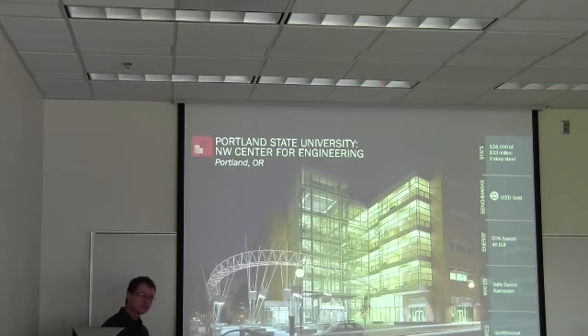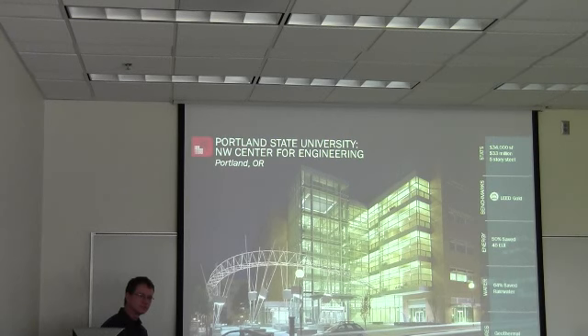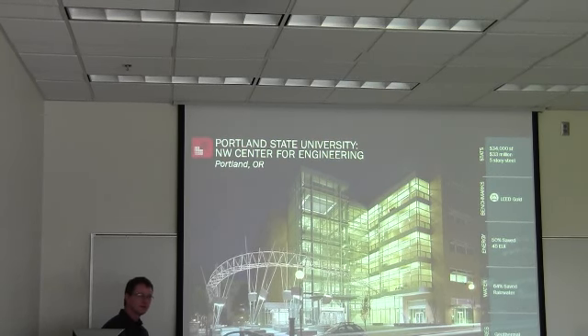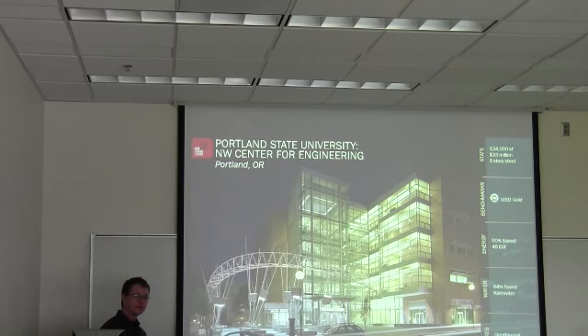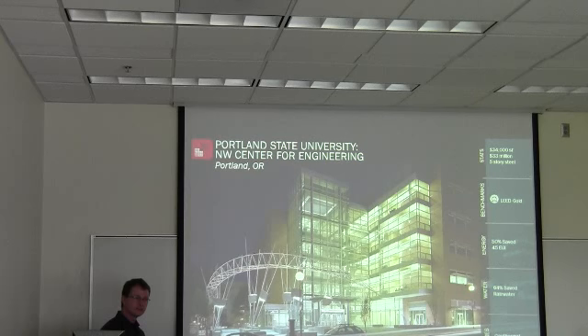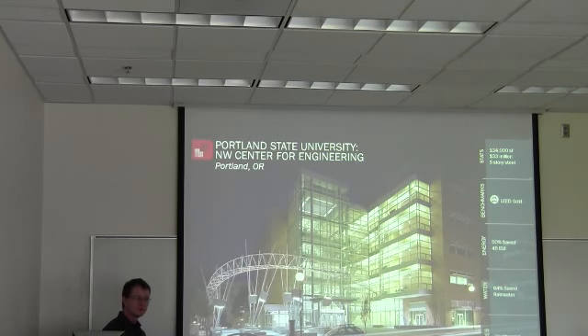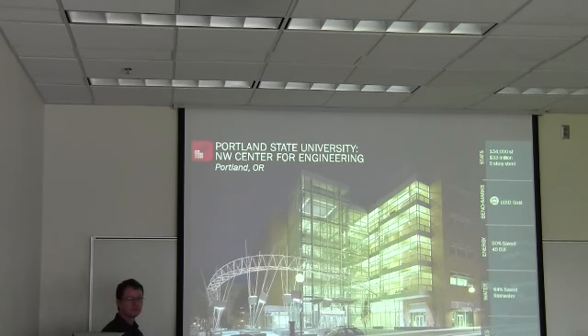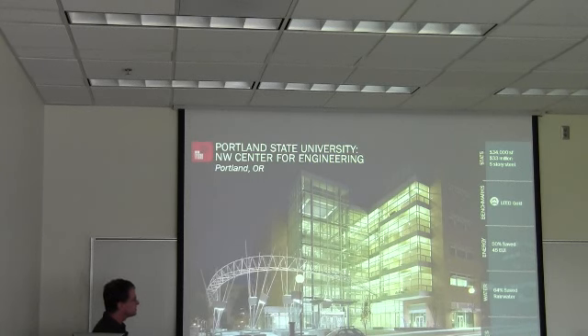One of those wells was existing when this building was built, and so two wells were added, one reinjection well and one well that draws water out of the aquifers. There's actually two aquifers under this building. We draw water out of one and reject the water into another one within the substructure. I think one's at 600 and the other's at 800 feet below where we're at now. So it's very interesting how that works.